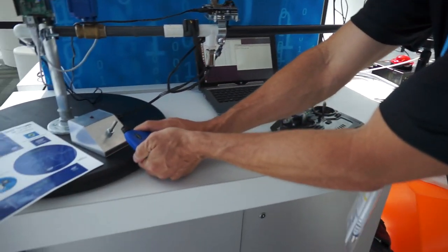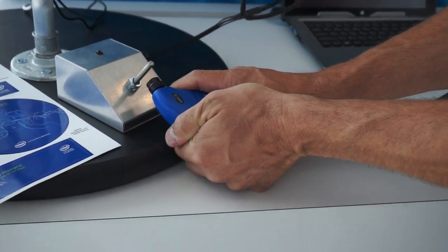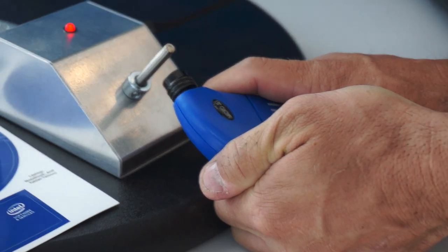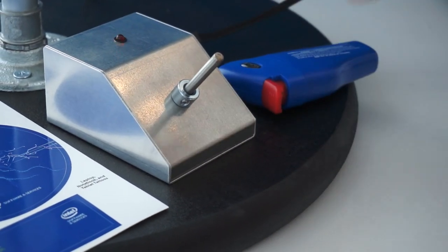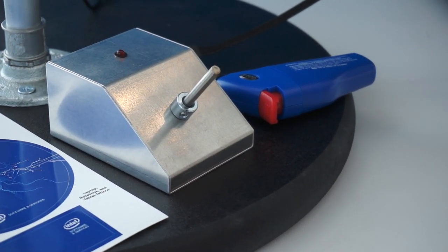So we have a fire scenario I can show you to kick off an emergency response. Taking a torch and heating up a heat sensor past a specific threshold. I've got an LED light on there to let me know when I'm past that threshold. So I'm going to go over there and pick up some data.